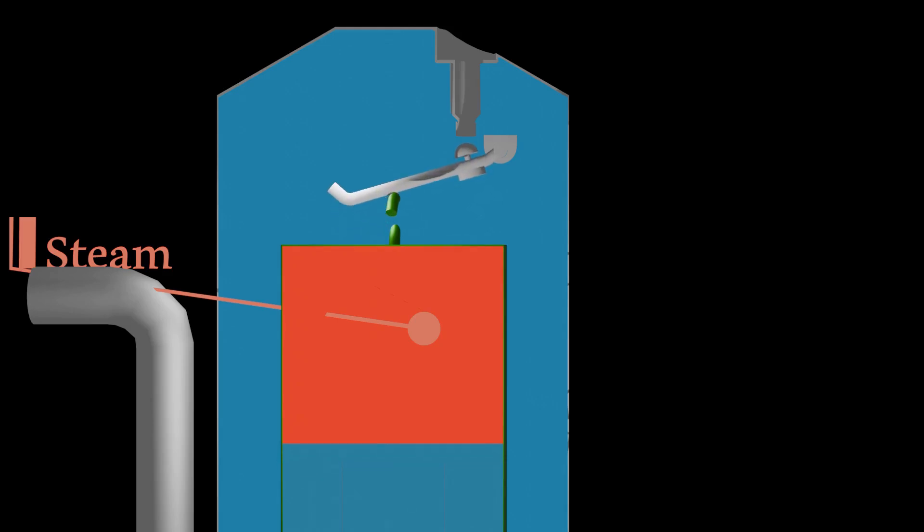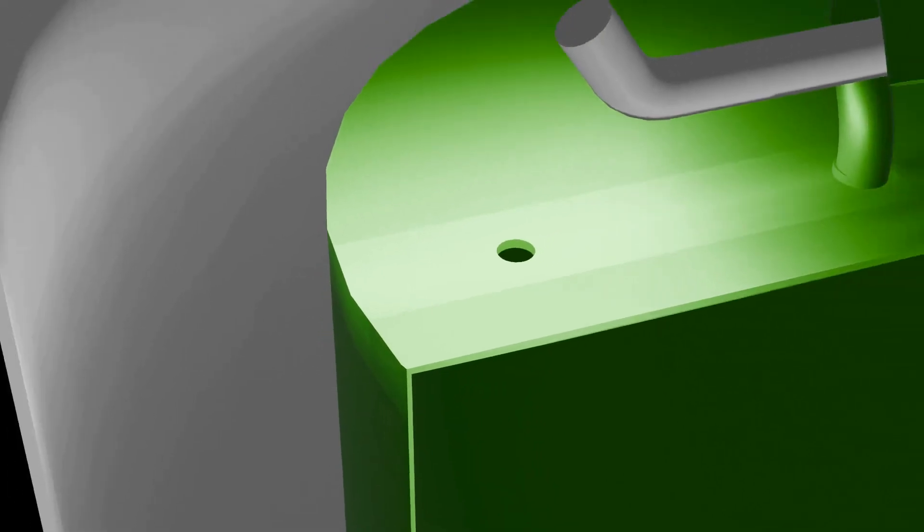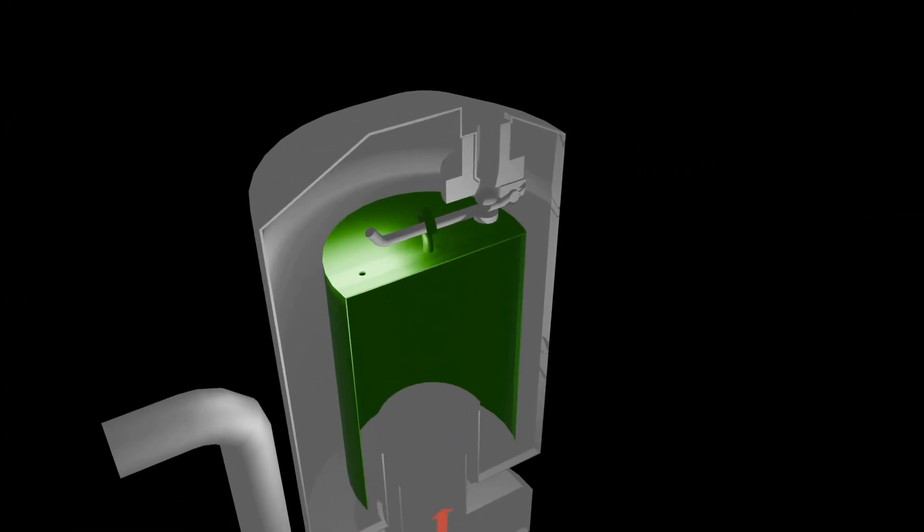One last thing is the small hole inside the bucket. This is used to relieve the non-condensable gases. One important question: what about the steam that escapes from this hole? The answer is that this amount of steam is so small that it will instantly condense as it escapes. Thanks for watching.